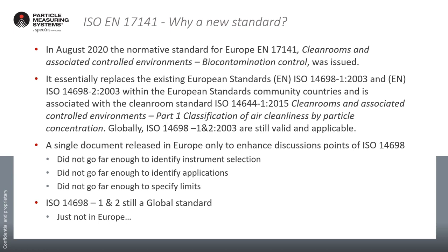One of the reasons they issued the new standard was because ISO 14698 didn't go far enough to fully identify instrument selection, the various applications associated with controlled environments by biocontamination control, or specify limits as to what the expectations were. It just required consideration of various techniques with no real guidance as to which techniques fitted into which arena. ISO 14698 parts one and two is still a global standard, just not in Europe.